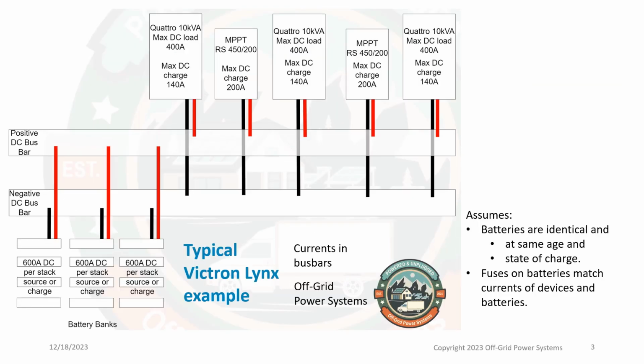Shown here is a typical configuration of a Victron system with a Lynx Power In on the left and a Lynx Distributor on the right. A Lynx Shunt or BMS could be between them. If we consider just the first Quattro requiring 400 amps of load, each battery supplies 133 amps. Note, we are only showing the positive bus bars for clarity. The negative bus bar currents will be similar, just the opposite polarity.